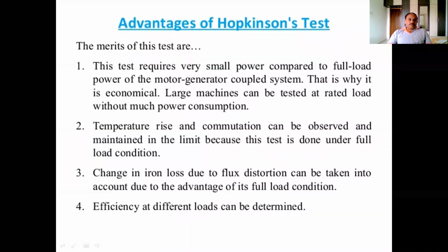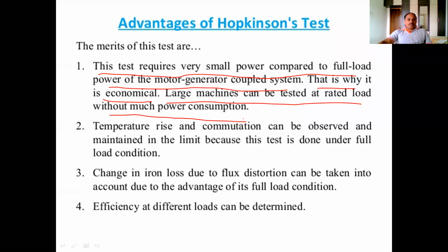The advantage of this test is that it requires very small power compared to full load power for the motor generator coupled system. That is why it is economical. Large machines can be tested at rated load without much power consumption, because in this test the power consumed is only to meet the losses. Next, temperature rise and commutation can be observed and maintained within limits, because this test is done under full load condition.